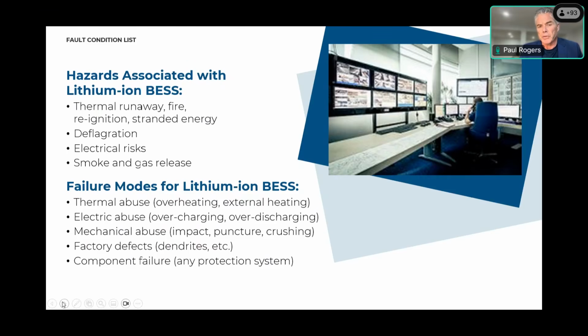Electrical risks are always a concern for any type of electrical equipment, and again we go to the fire department to make sure they understand that on their end. Like any fire, smoke and gas release is typical with any type of failure that may take place with a battery energy storage system, even though we recognize it here specifically in lithium-ion.